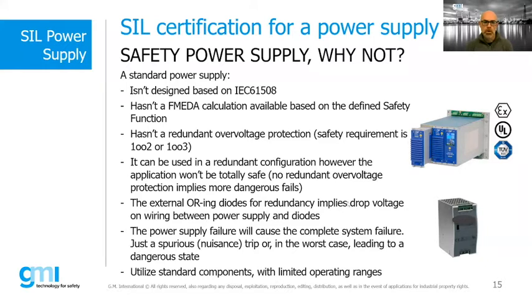We know well that a spurious fault can also lead to dangerous failures for the application. And again, standard power supplies use internal components with a limited operating range to keep cost down. This affects the lifetime of the device. For this reason, internally to the safety power supply, components with a higher operating range are used that allow the system to work at a lower stress level. This leads to fewer failures and consequently a considerably longer life than a standard power supply system.